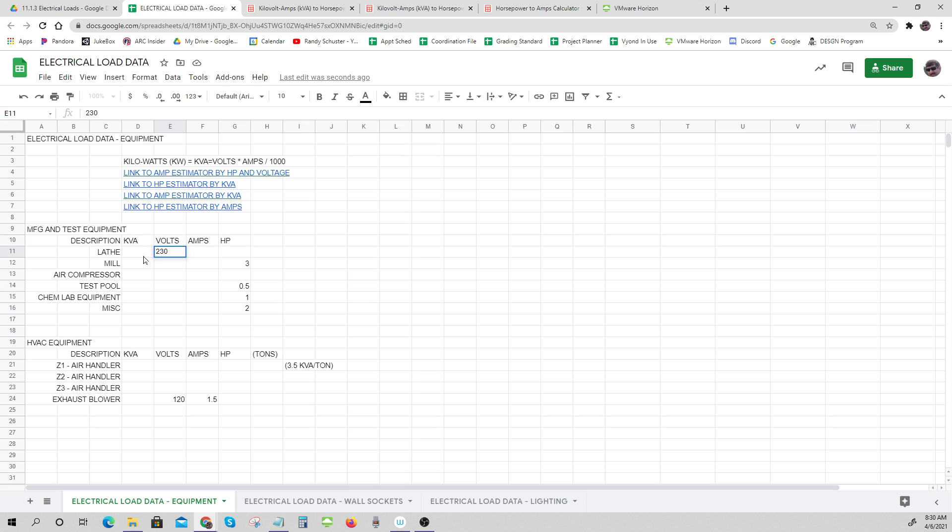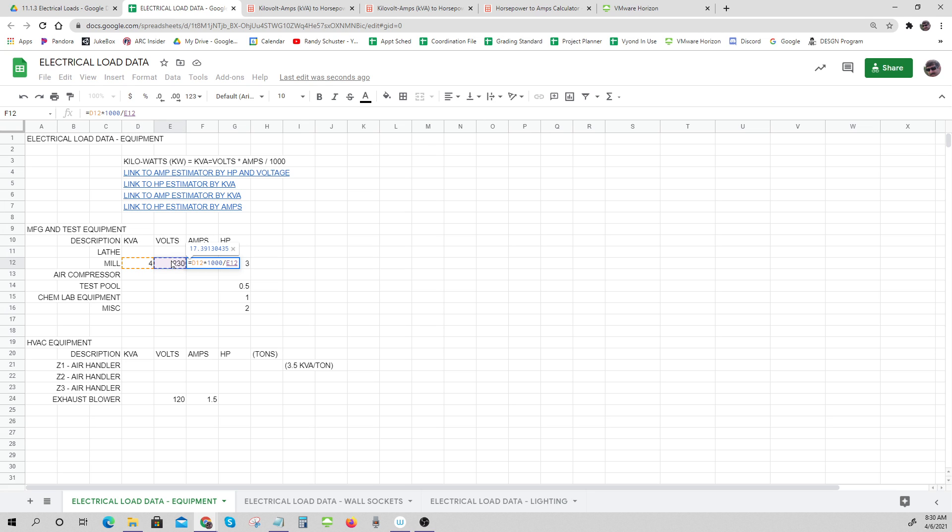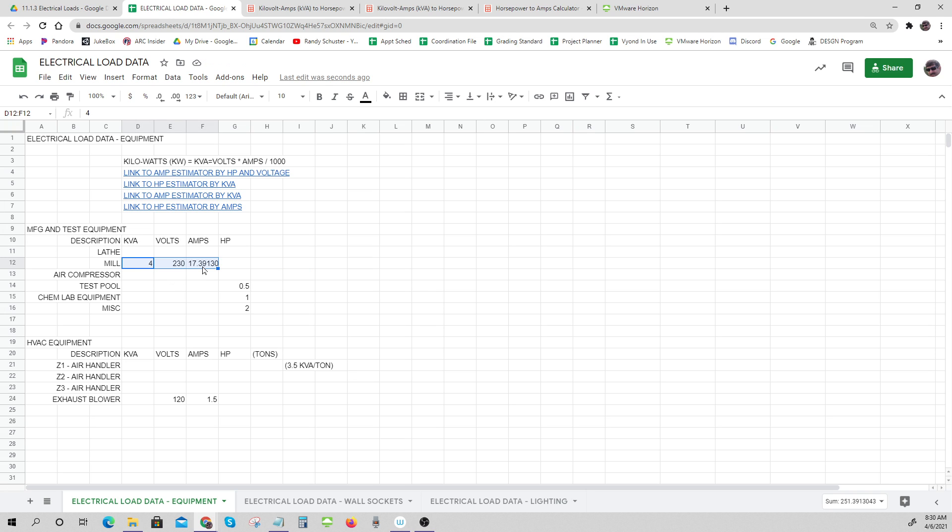That's on the mill: 230 volts, 4 kVA. So what is the amps? Amps equals kVA times a thousand divided by volts, equals kVA times 1000 divided by the volts - 17 amps. And then I could go back and get my power off of that. So that's how you're going to do it. There's all your formulas and everything up here.